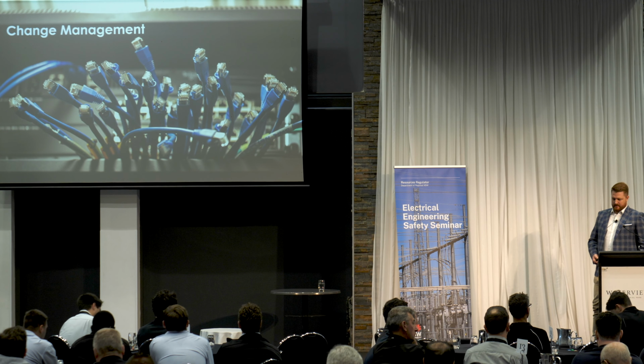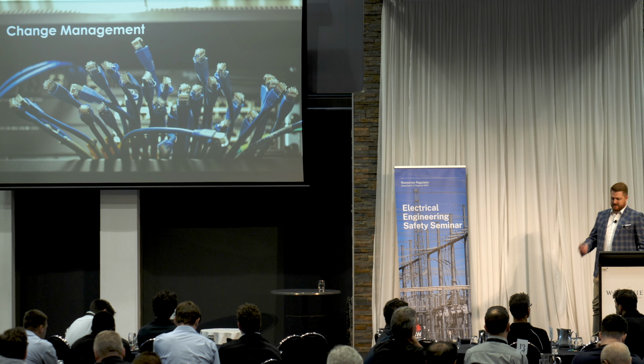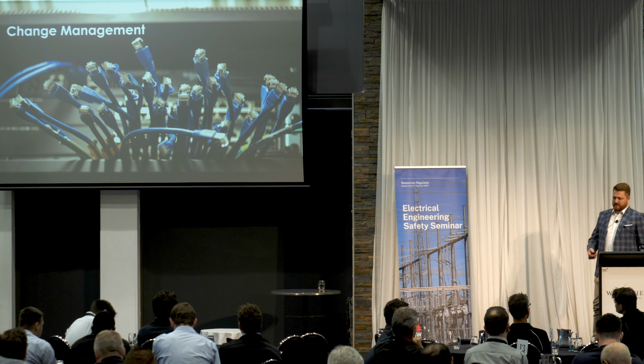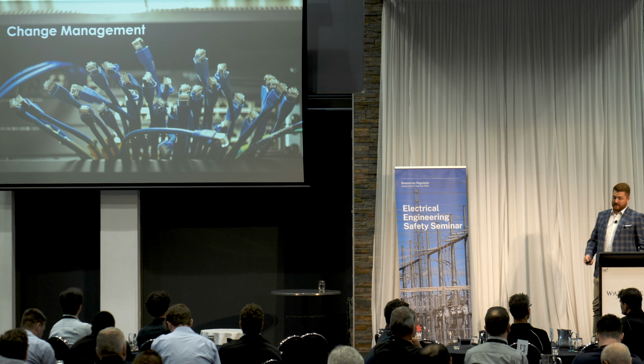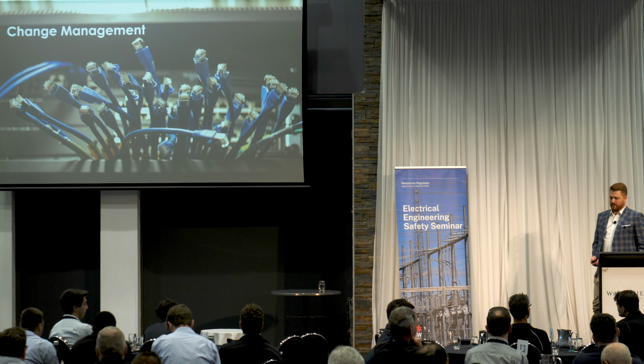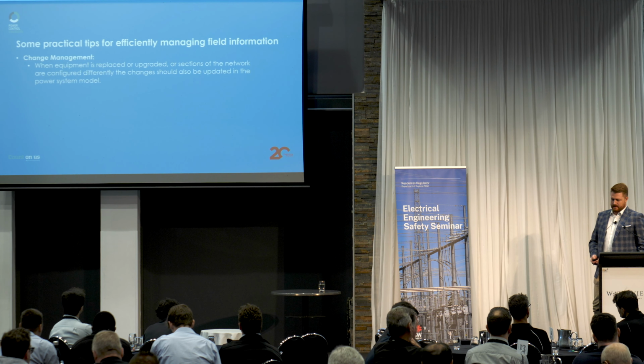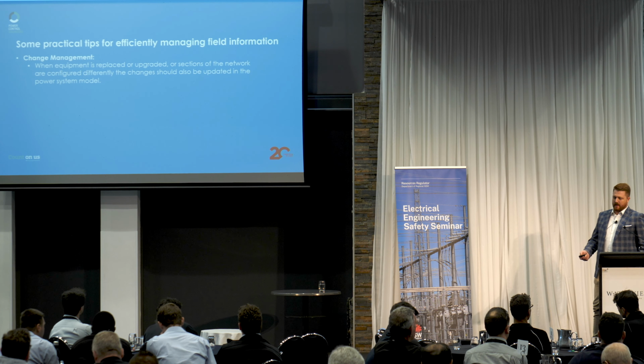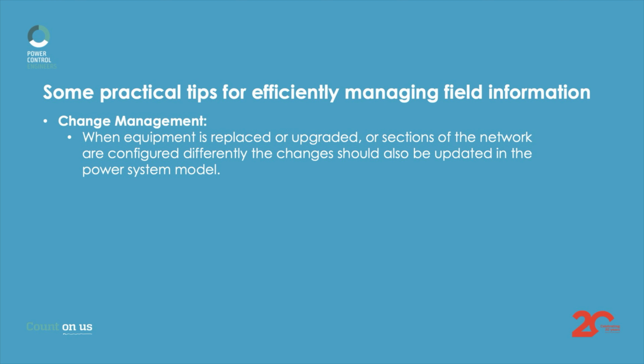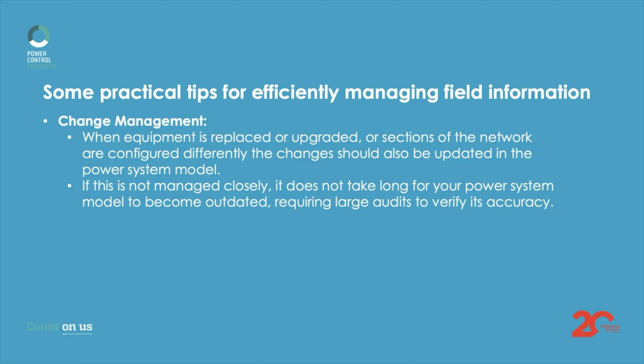And the third strategy is change management. For sites where the power system model has been accurately modelled already, it's important to consider change management. So when equipment is replaced or upgraded or sections of the network are configured differently, the changes should also be updated in the power system model. If this is not managed closely, it does not take very long for your power system model to become outdated. And then once it's outdated, it will require a large audit to verify its accuracy.